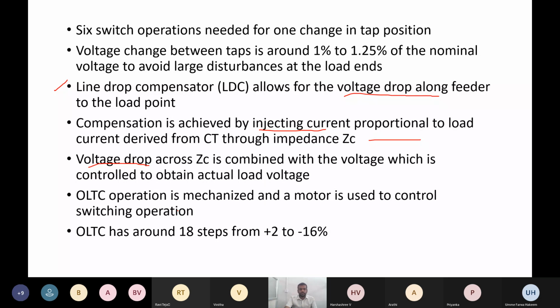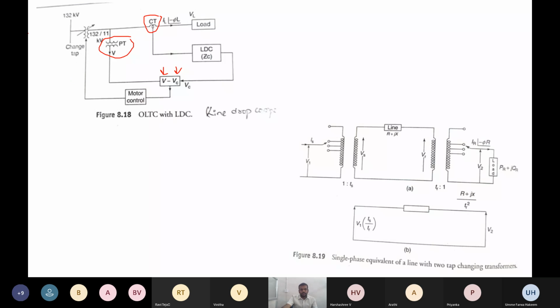And also one more thing, the OLTC should be operated around 18 steps, from +2 to -16. So this is the thing. So CT will be there. So from the CT we will measure the actual current. So by measuring that actual current in the load side, LDC will be there. So this LDC injects the required amount of current. So that current will be supplied by the tap changers. So this is our tap changing transformer.